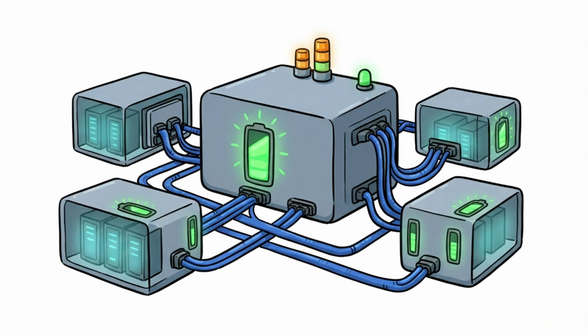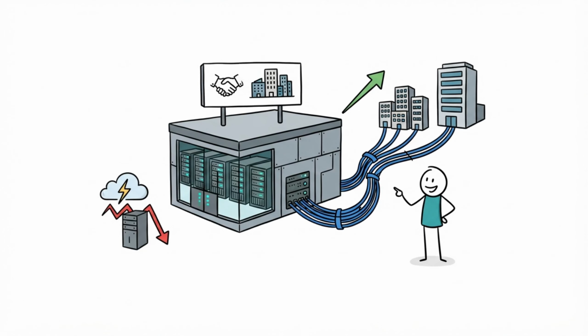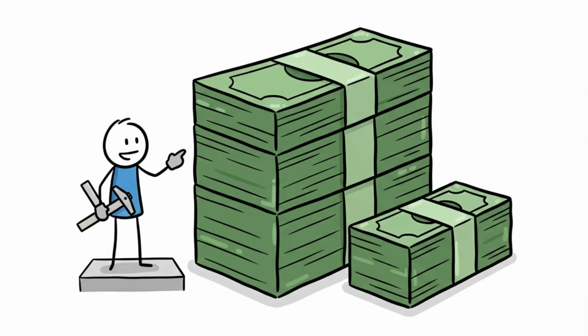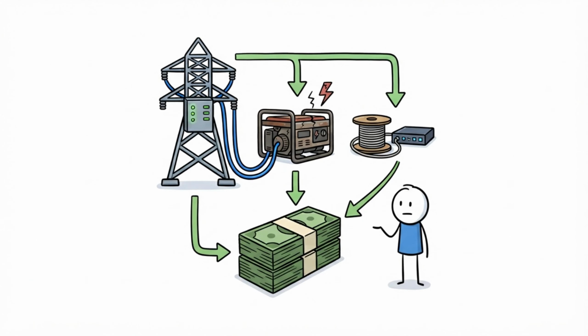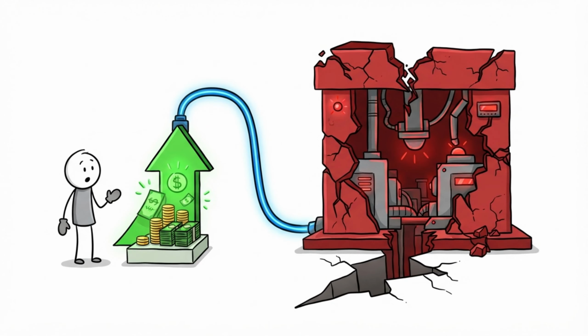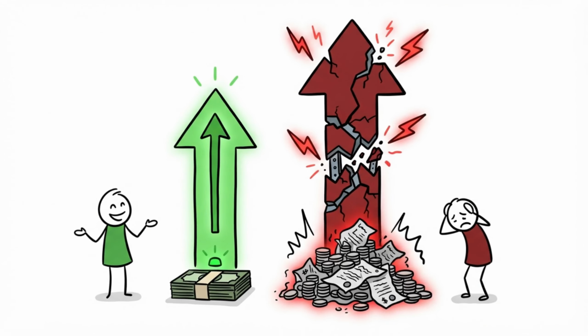Start with a real mid-size co-location facility, 2 megawatts of critical IT capacity, the kind a regional operator builds to serve enterprise and mid-market customers, not a hyperscale campus chasing a single cloud tenant. Construction alone at the 2025 industry benchmark of roughly $11 million per megawatt for a standard shell and core build with N+1 redundancy runs $22 million.